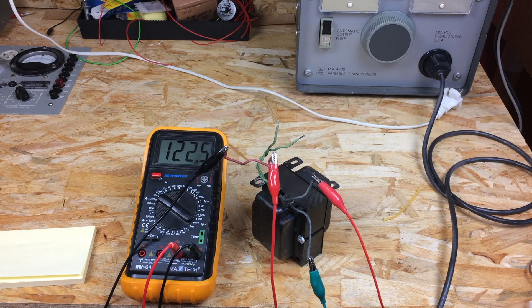Before taking the transformer apart, I wanted to check the no-load voltage, so that I can rewind it as close to the original as possible. Being very careful not to touch any of the leads while the transformer is on, I connected the voltmeter to each of the leads and took the readings at 115 volts on the primary.